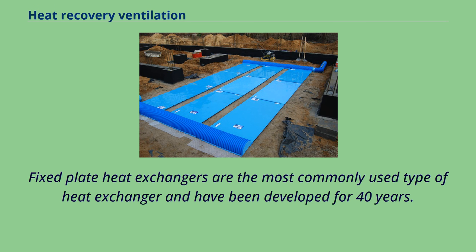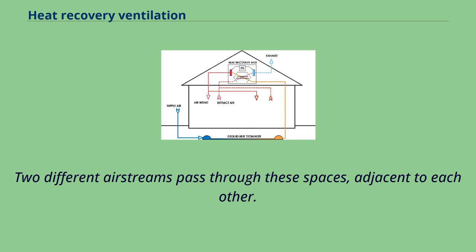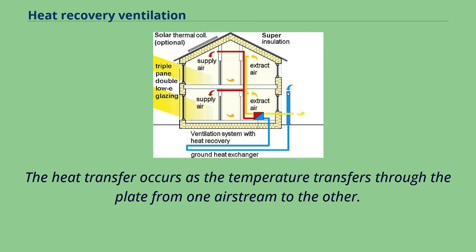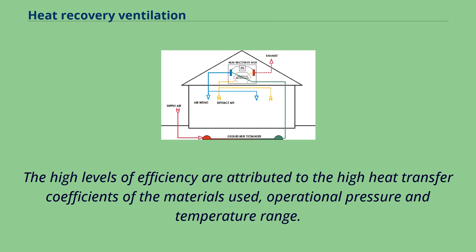Fixed plate heat exchangers are the most commonly used type of heat exchanger and have been developed for 40 years. Thin metal plates are stacked with a small spacing between plates, and two different air streams pass through these spaces adjacent to each other. Heat transfer occurs as temperature transfers through the plate from one air stream to the other. These devices have shown 90% sensible heat efficiency, attributed to high heat transfer coefficients of the materials used, and their operational pressure and temperature range.